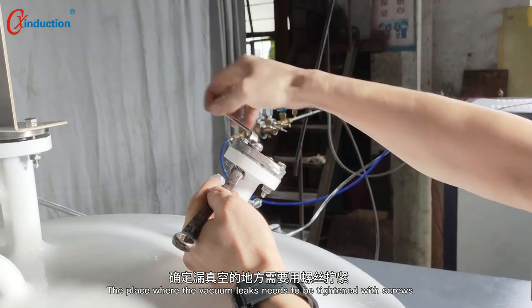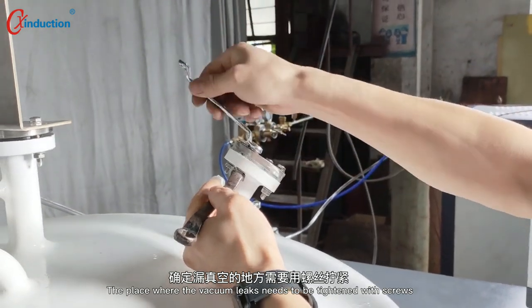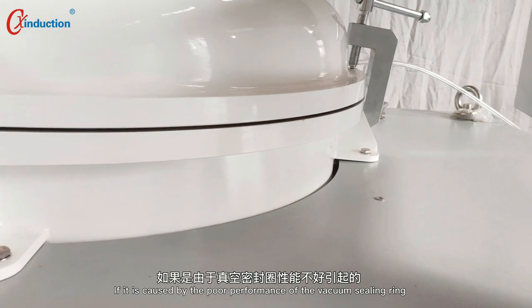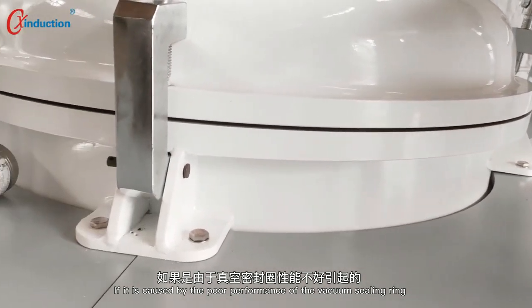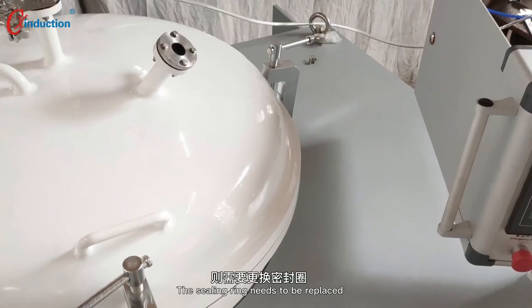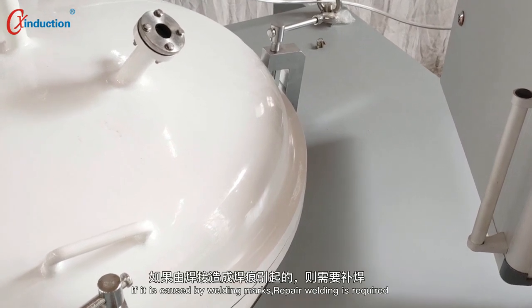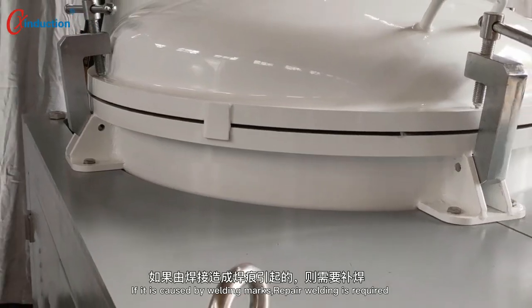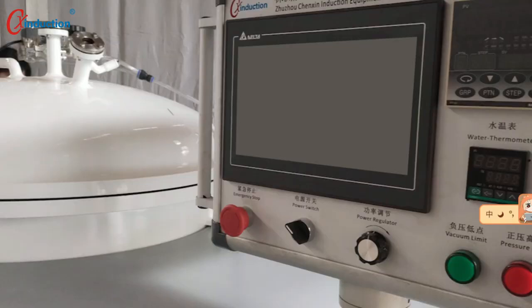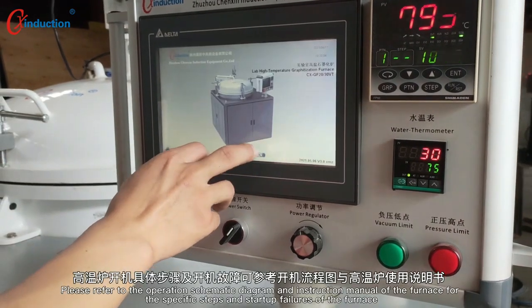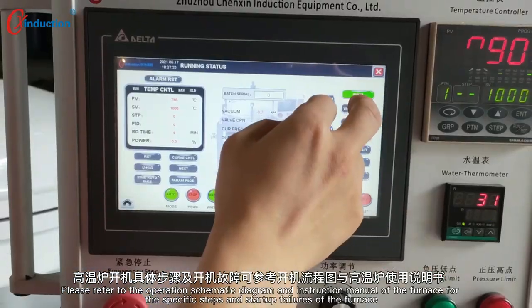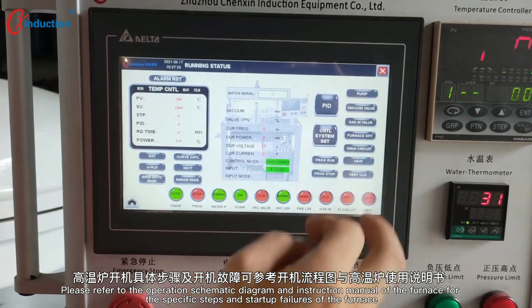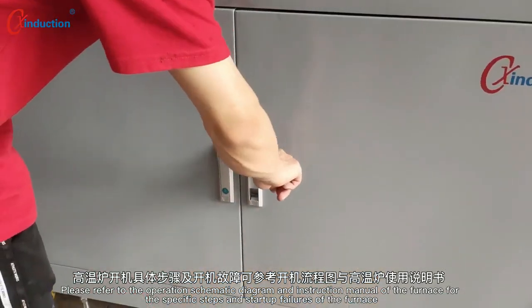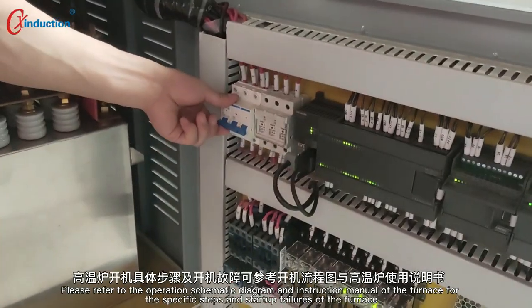The place where the vacuum leaks needs to be tightened with screws. If it is caused by the poor performance of the vacuum sealing ring, the sealing ring needs to be replaced. If it is caused by welding marks, repair welding is required. Please refer to the operation schematic diagram and instruction manual of the furnace for the specific steps and startup failures of the furnace.